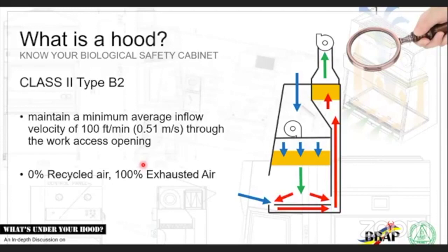So this is very unidirectional. Your blower here sucks in room air from the top, pushes it down to the filters, generating a clean air space here. If contaminated, they go inside two vents, your front grill and your rear grill, get sucked in. This is a very good negative pressure plenum because it is being sucked in and out by a blower on the top.